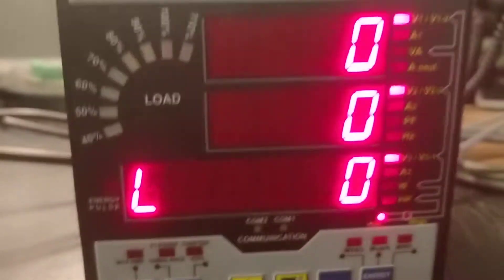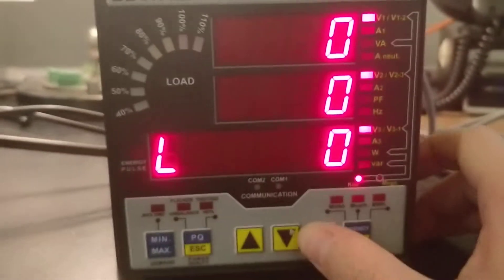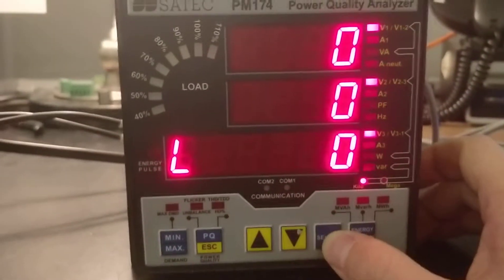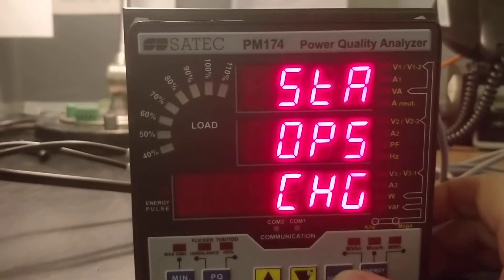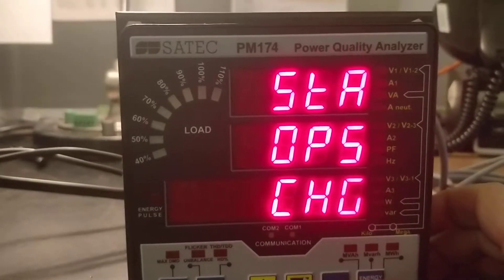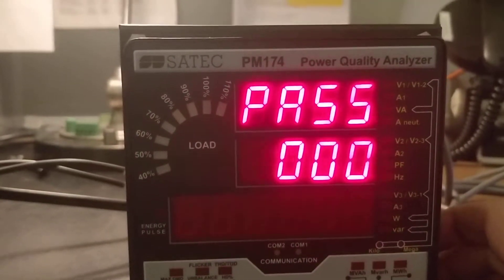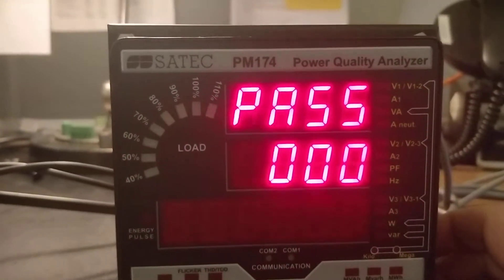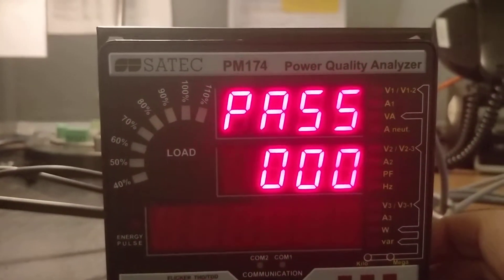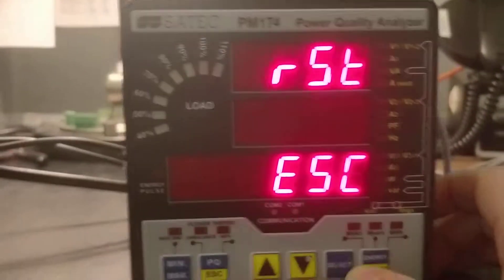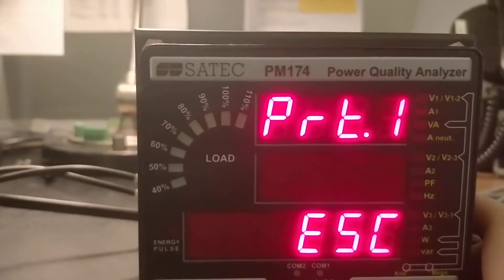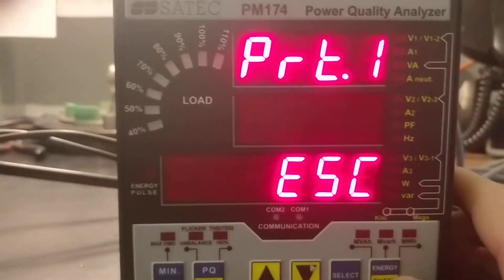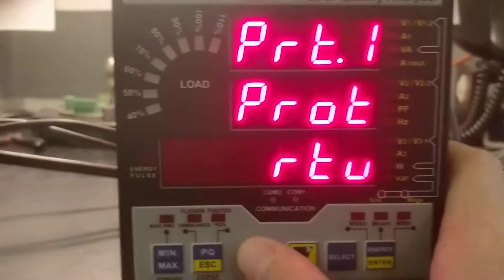Okay, we're going to go through the front display settings of the meter to get the configuration. You're going to hit select three times until you get to CHG. Password is zero unless you have a custom password. Up arrow until you get to port one. Hit enter.